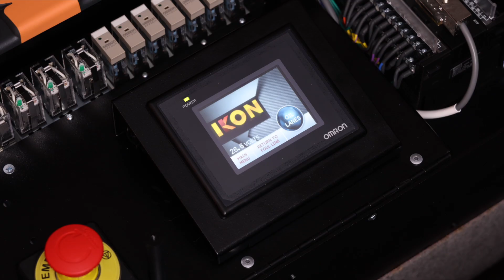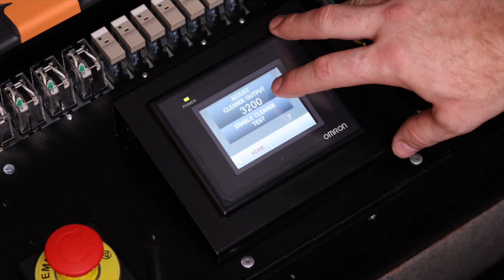First, we'll go to Main Menu, and then Cleaner Oil Calibration, and finally, Cleaner Calibration. First, we'll go over the screen. At the very top, you have your analog value. The higher the number, the higher the output, and vice versa for the lower number. The Enable Cleaner Test button, which will be enabled before we run the test. And finally, the amount of times the test has been ran.